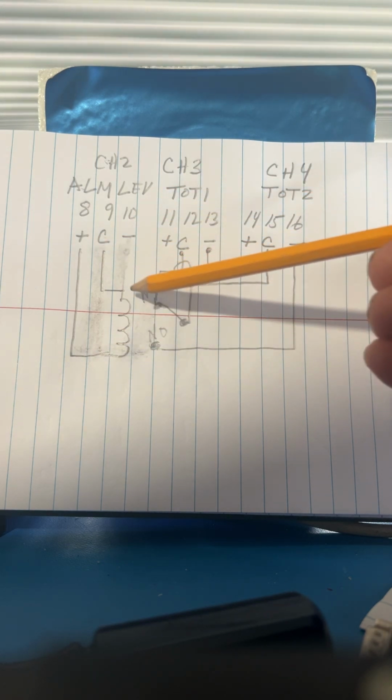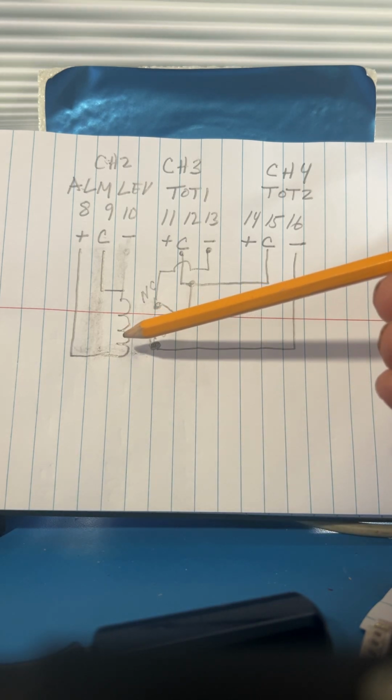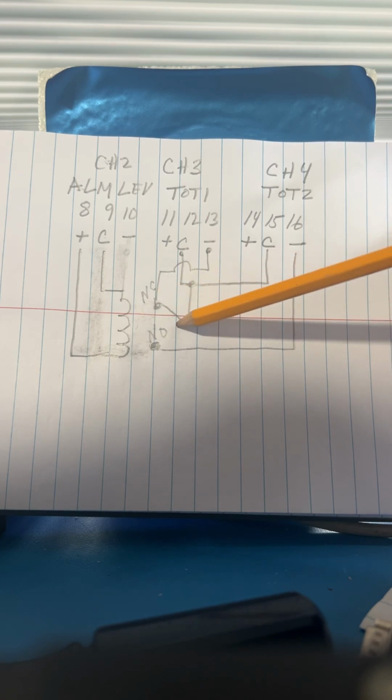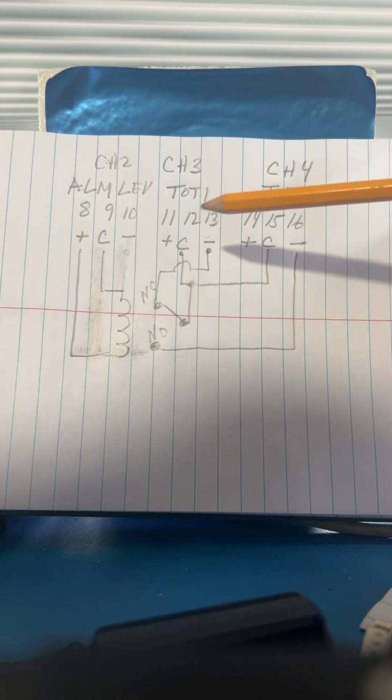So here's a schematic which helps understand this a little bit better. Channel 2, which is your alarm level, which is how you're going to trigger either below or above the sound velocity. The coil, this is the relay coil, will either be de-energized or energized. So if you're not in an alarm condition, then of course it's de-energized, and then the normally closed relay is going to stop totalizer 1, let's say.